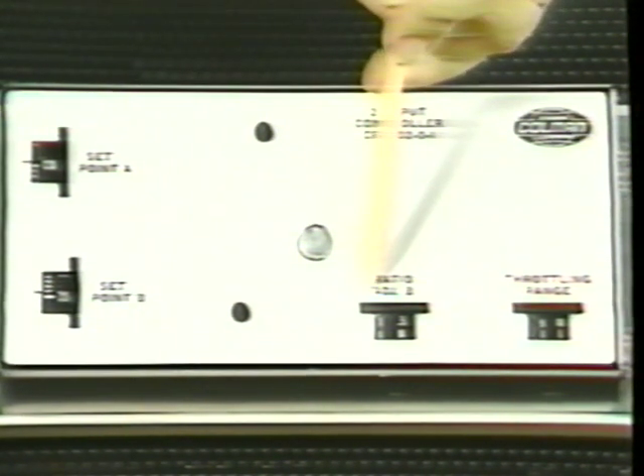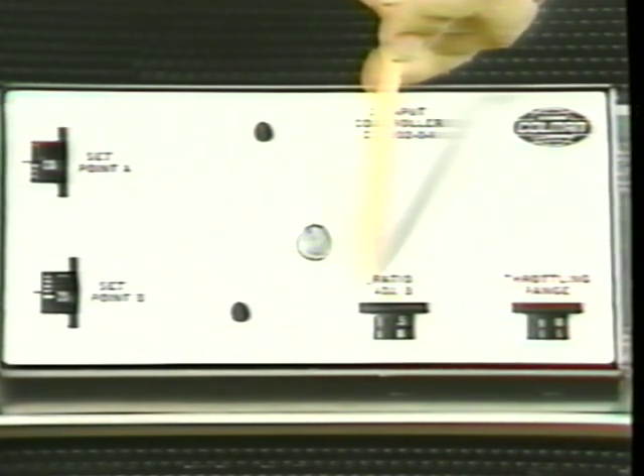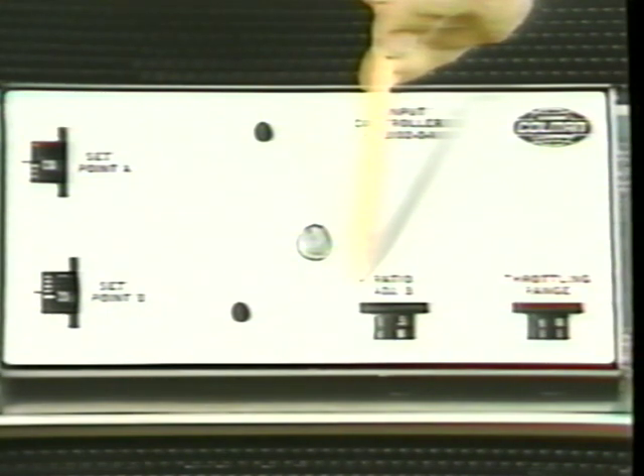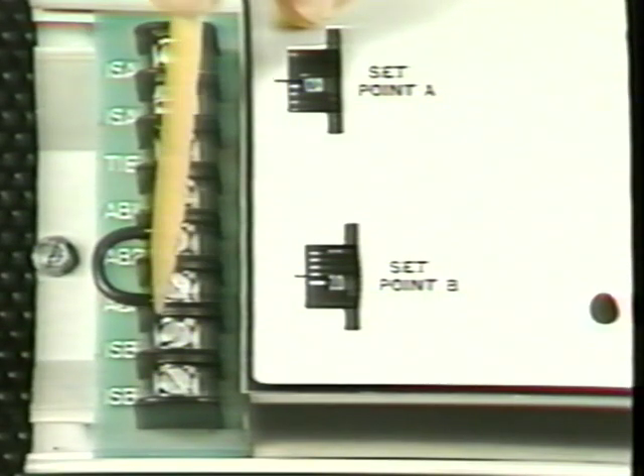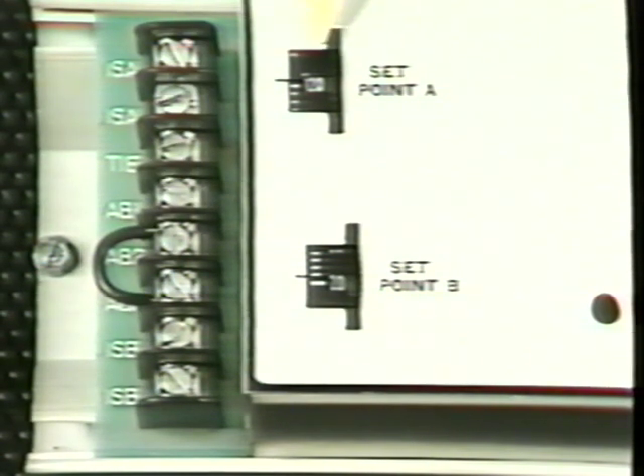Ratio adjustment B. This variable adjustment determines the effect of sensor B in reset applications and is adjustable from 0.5 to 25, representing the ratio of bridge B to A, with A always taken as 1. For example, a setting of 0.5 means B to A 0.5 to 1, or for every 1/2 degree Fahrenheit change at sensor B, the effect on the controller will be a reset of set point A by 1 degree.